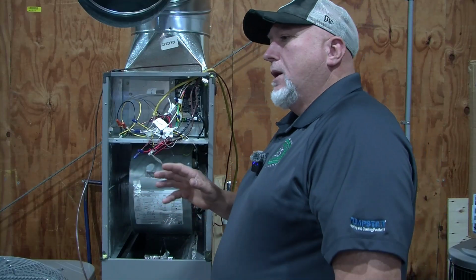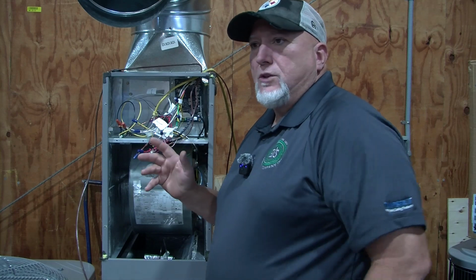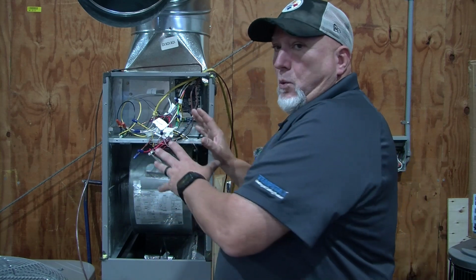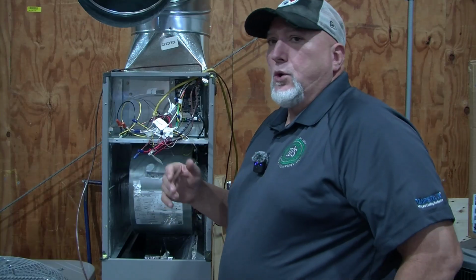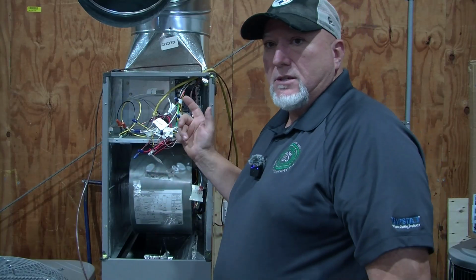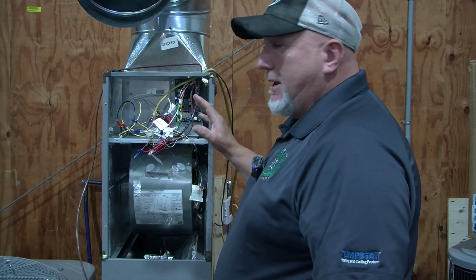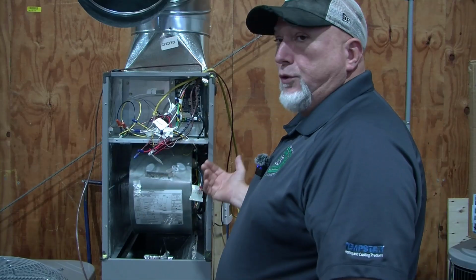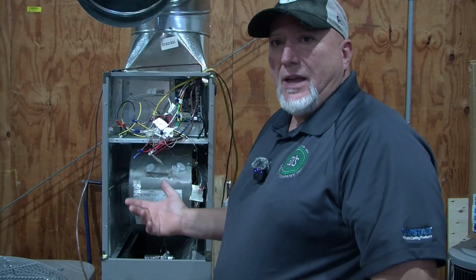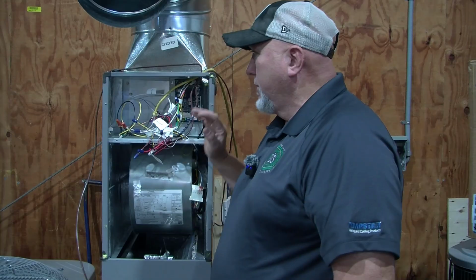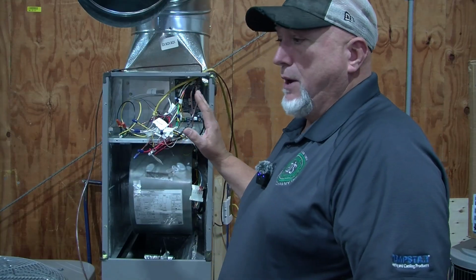So that's why when we install these, we always want to make sure we got it wired up right, and then we're going to go through the test process, and we're going to test cooling, and then it's going to come back, and at the end we'll make sure the condenser unit comes on, and then you go through a heat cycle, test it in the heat cycle, make sure it comes back on, and your heat kicks on like it's supposed to. And then we're going to talk about airflow.